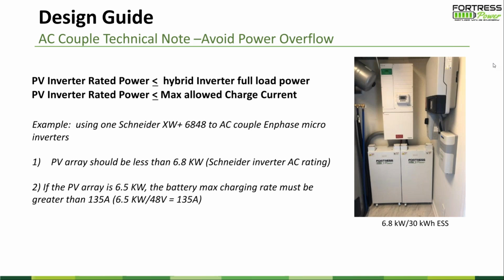If you have a 5 kW inverter and a 5.5 kW PV array, you want to match those with your energy storage - maybe 6.6 kilowatt for the PV array to match with the battery bank. Let the battery bank be bigger than the PV array, and let the energy storage inverter's rated power be bigger than the PV inverter's rated power. That's the technical note - when we design, we really want to pay attention to it. I know the inverter company will tell you no problem, frequency shifting, but in real life you want to pay attention to this. Okay, next slide.